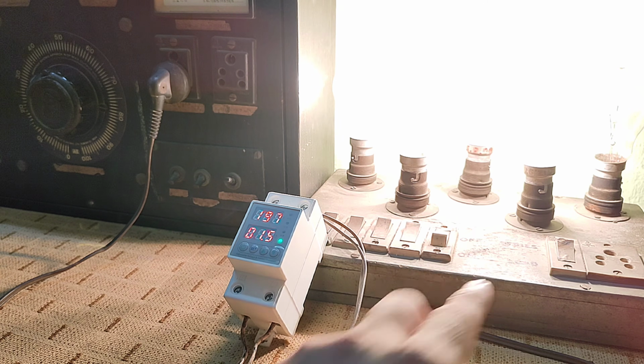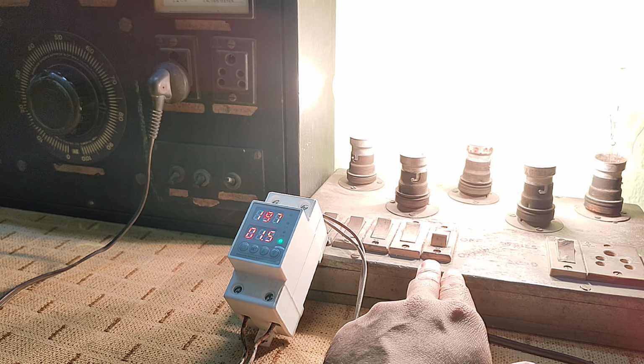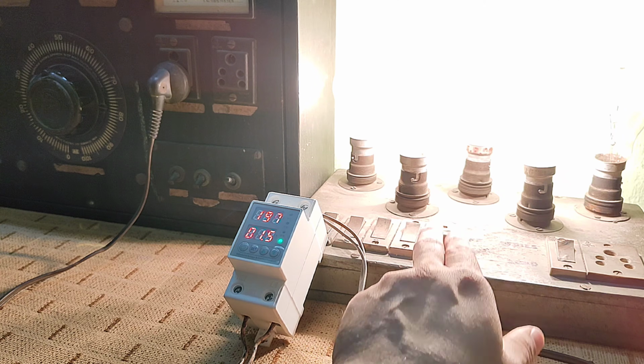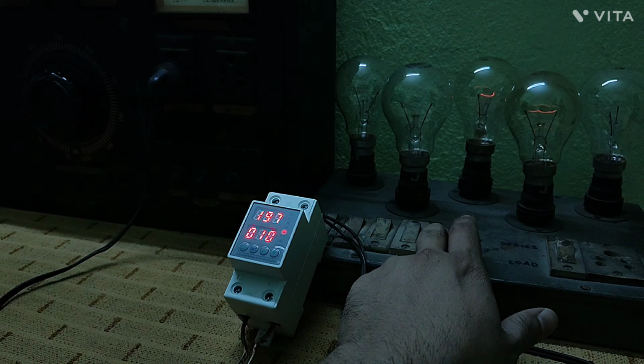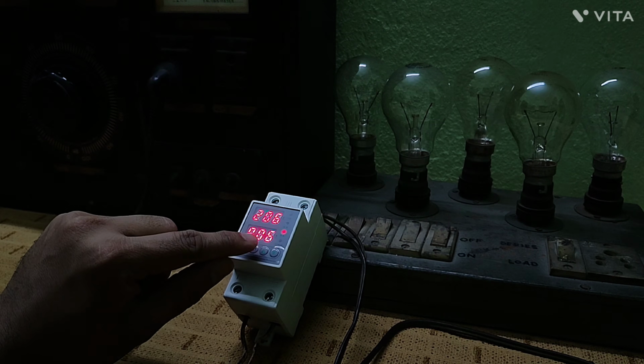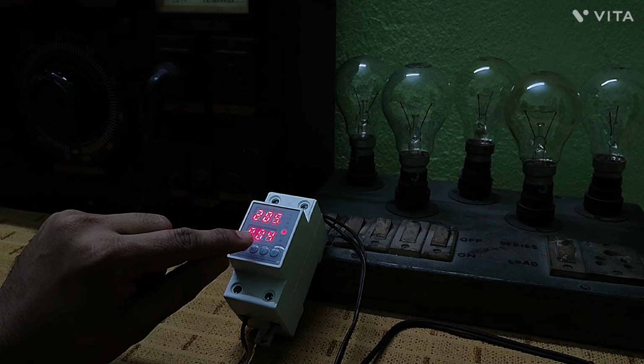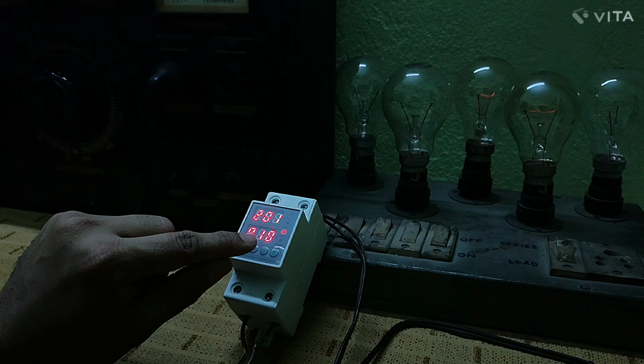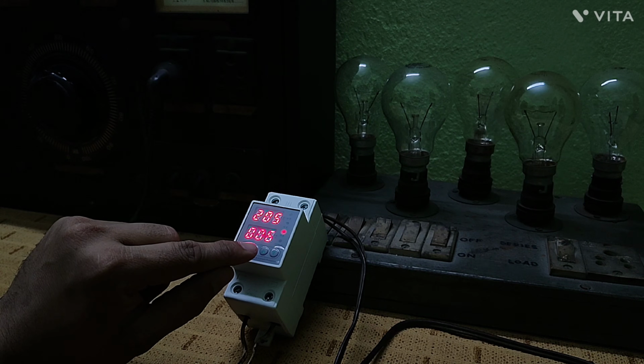So now as soon as I power on the 5th bulb, it will automatically trip. You see, it automatically got tripped. I set it to 10 seconds as the delay time to check again if the power issue or short circuit is still there. You see, it tripped off again and the countdown started again. You can change this delay from settings.